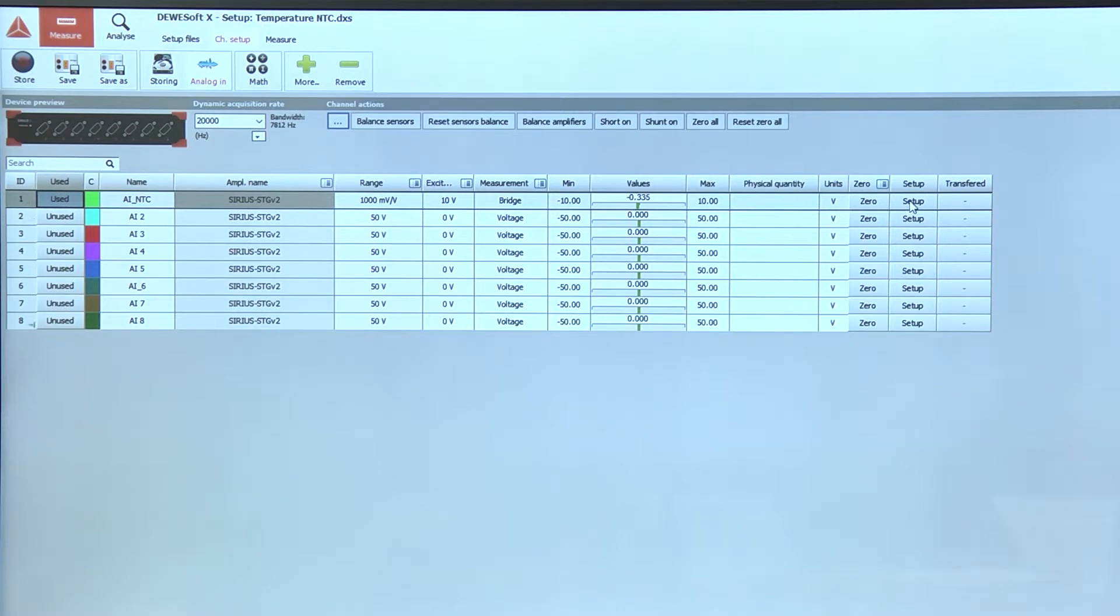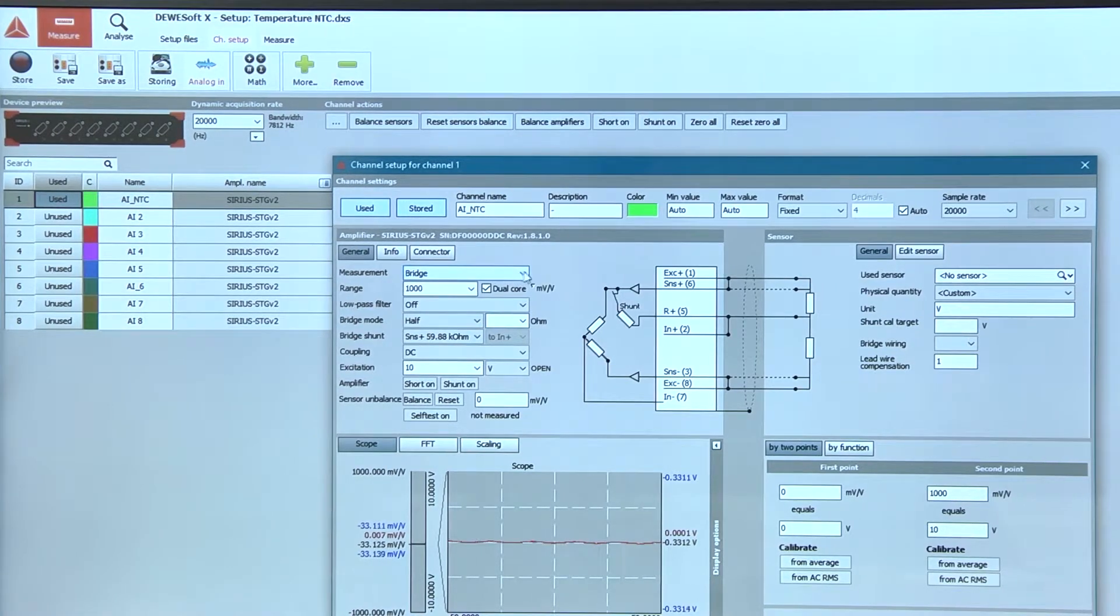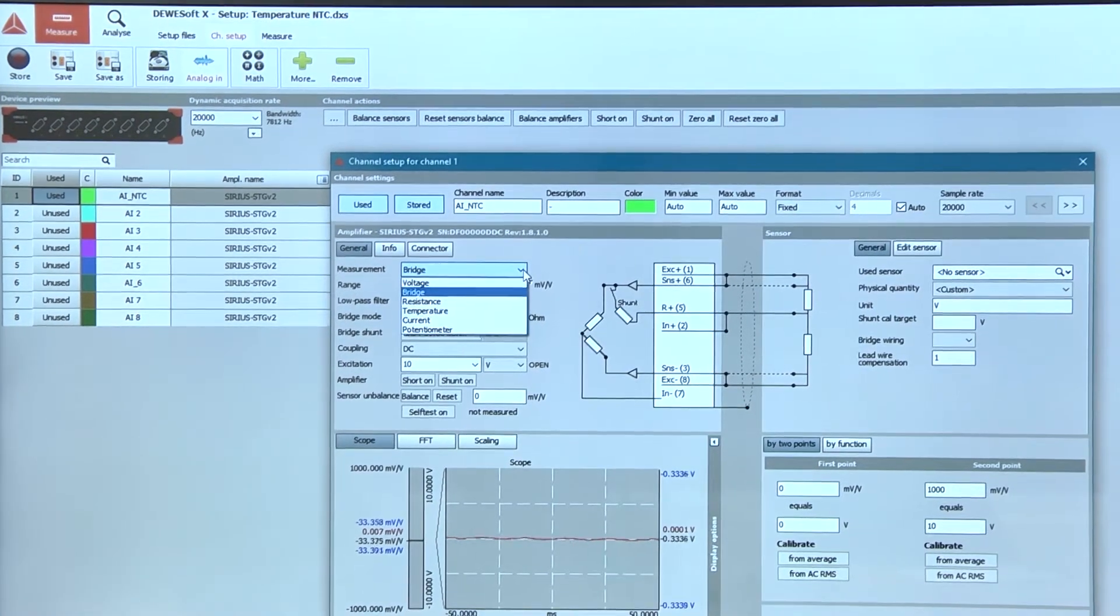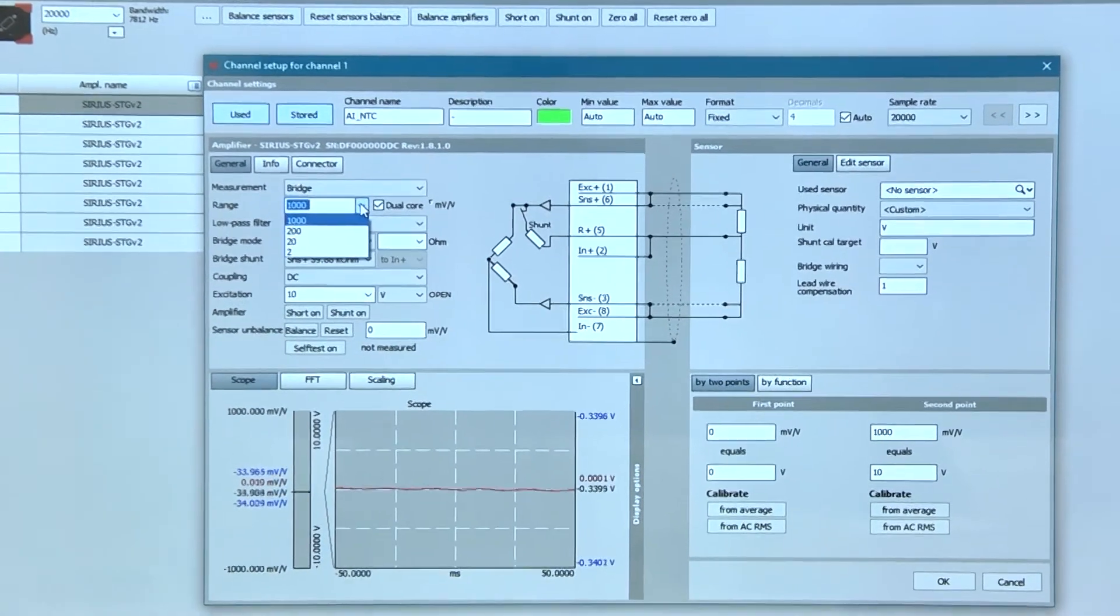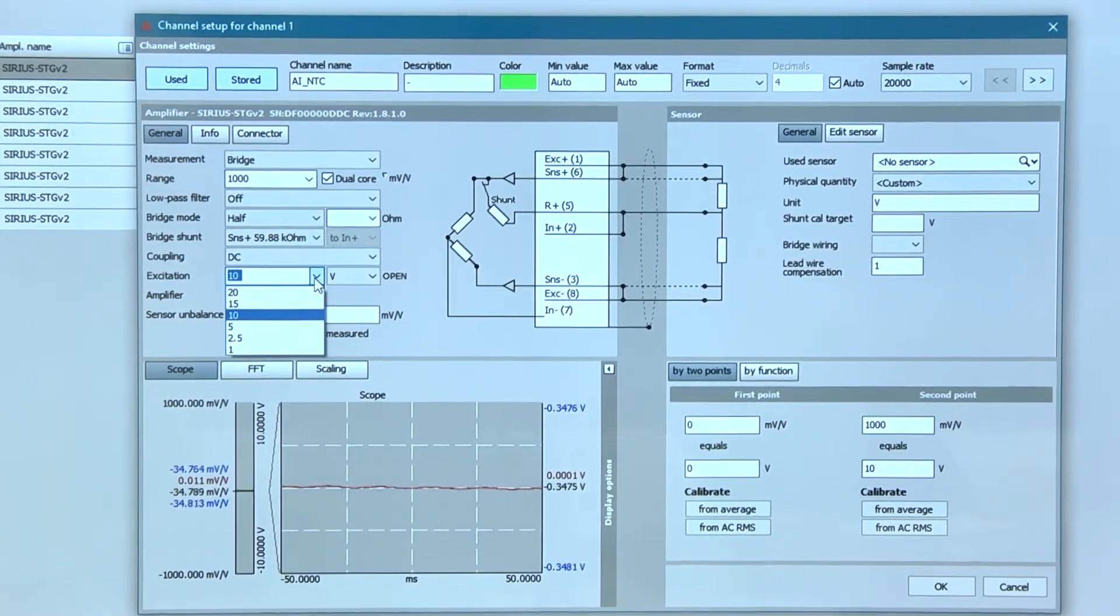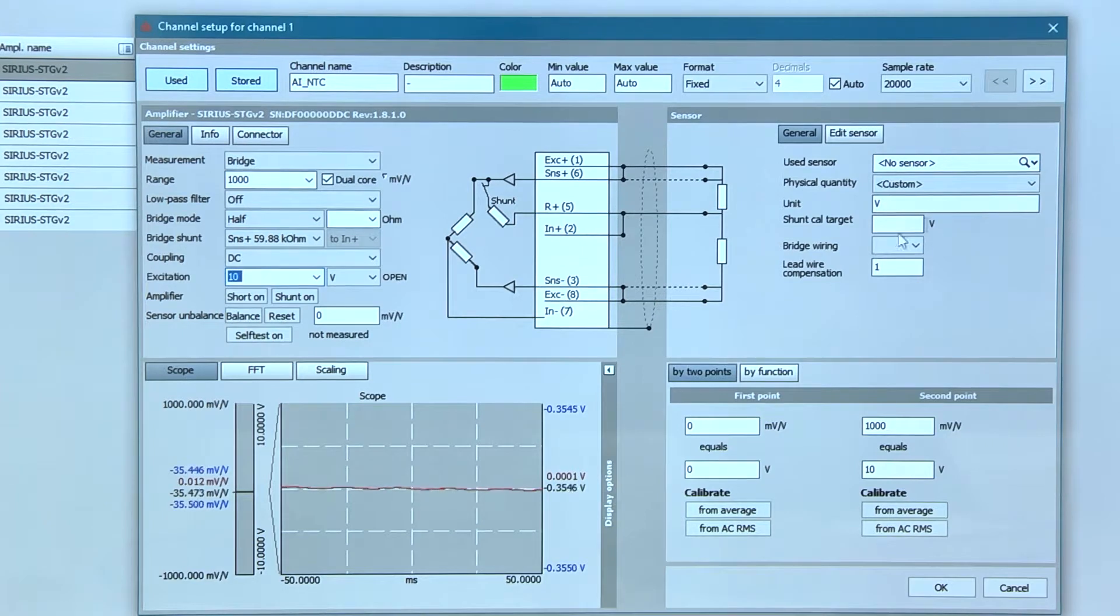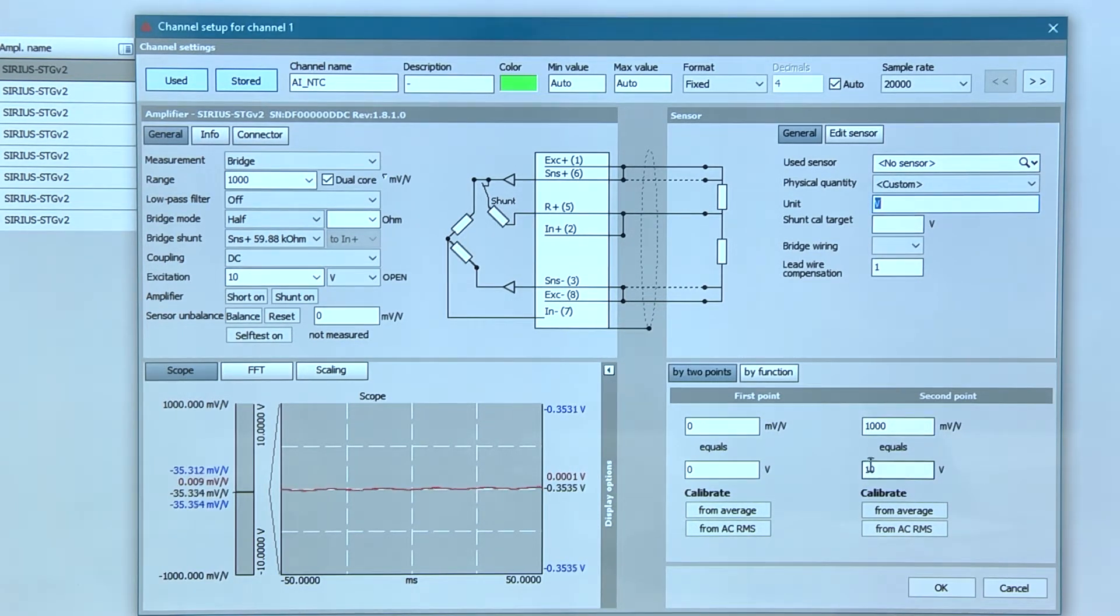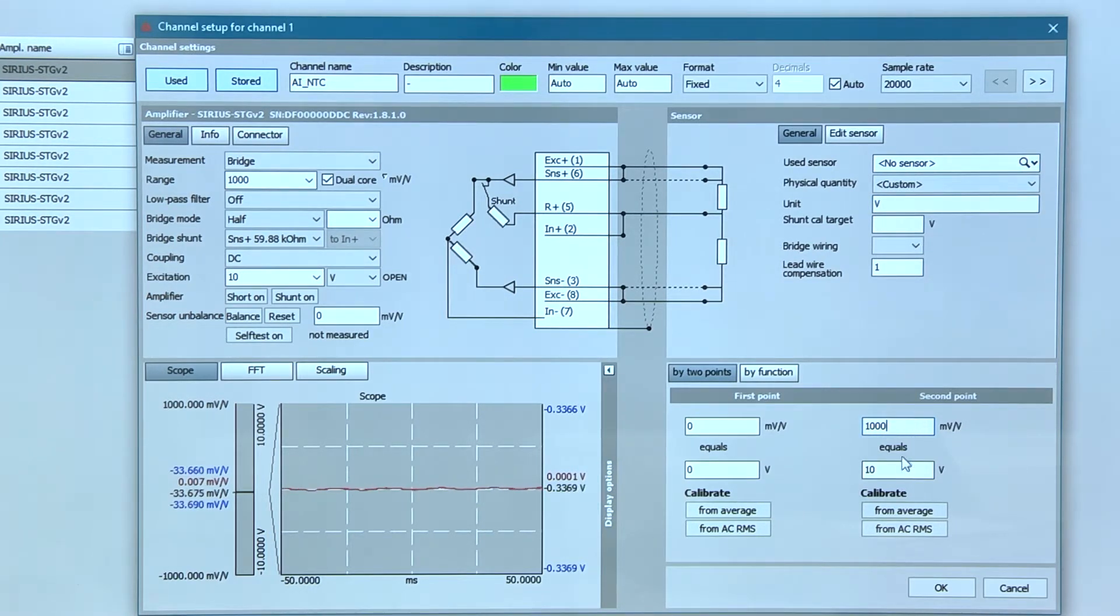First you must set up analog channel. In channel setup, you must select bridge measurement type, set range to 1000 mV per volt, set excitation to 10V, set units to volts and by two points setup 1000 mV per volt equals 10V.